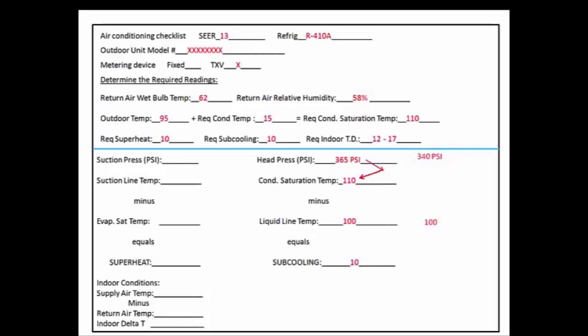But what if these are the pressures we got? We were reading 340 psi. Our actual liquid line temperature was 100. What kind of numbers are we looking at now? Well if we convert 340 psi using our pressure temperature chart, it converts to 105 degrees condenser saturation temperature. We subtract the 100 from that, and that gives us 5 degrees of subcooling.